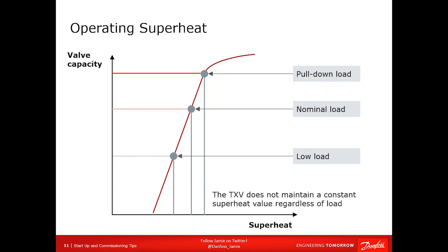So if you're going to ascertain the performance of something, everybody likes to measure superheat, and it is important. One thing you have to remember is superheat is not constant. Now, we can fool around with some bulb charges and minimize superheat change, but the reality is, if the system is heavily loaded, if you load 500 pounds of warm meat or beef or something into a cooler, that load will drive up your evaporator pressure. It will drive up your superheat, because that's the only way to open that valve up more. After it runs for 12 hours all night, you come back in the morning, your superheat could be quite low because there's no load on the evaporator, and the valve might only be open 20%.